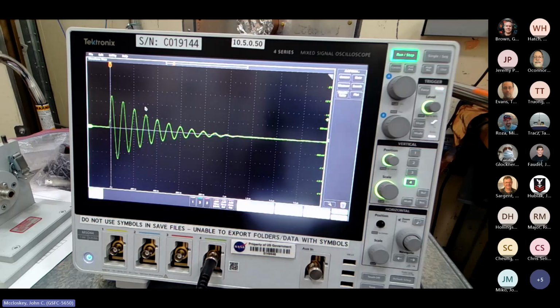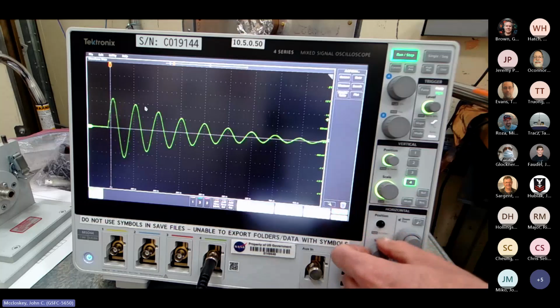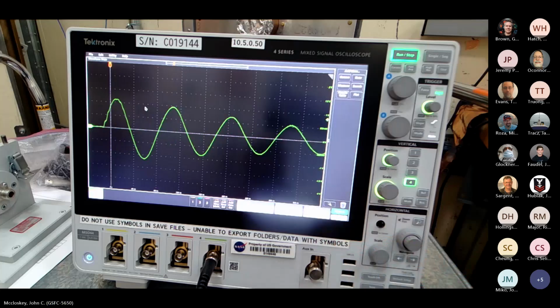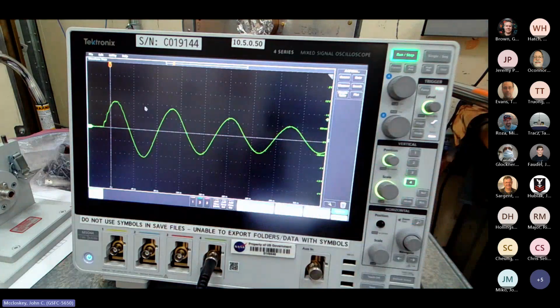So I'm going to go ahead and adjust the level so that we're getting closer to our 1 volt. We can adjust our horizontal resolution to get a little better look at that first peak. And again, when you select these waveforms to put in the test report, you can take as many scope captures as you want. Nothing says you've got to capture everything in one capture. So I'd be inclined to get something like this, to get a good look at the first peak.